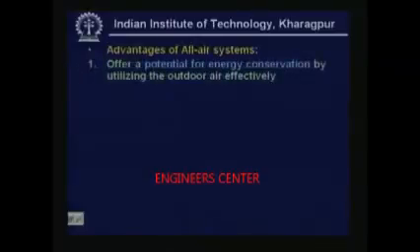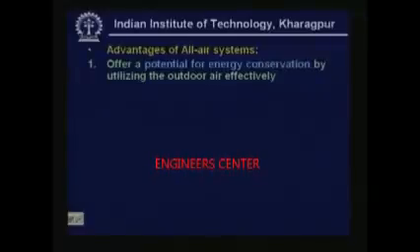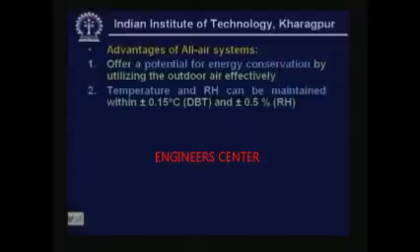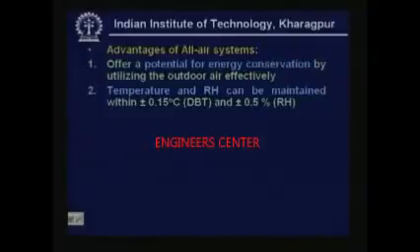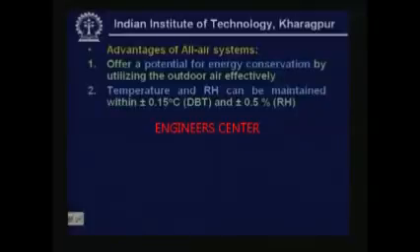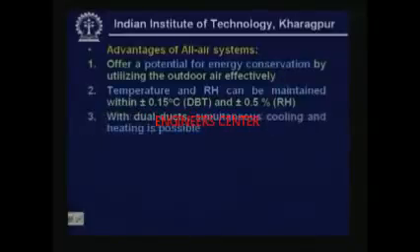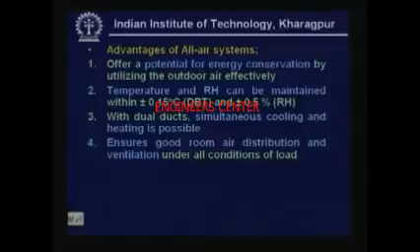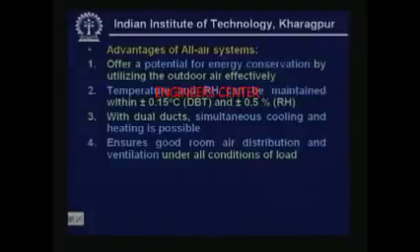Now let us look at advantages of all air systems. All air systems offer a potential for energy conservation by utilizing outdoor air effectively as just mentioned. Temperature and relative humidity can be maintained very precisely — temperature within plus or minus 0.15 degrees centigrade and relative humidity within plus or minus 0.5 percent — very close control. And with dual ducts, simultaneous cooling and heating is possible. All air systems also ensure good room air distribution and ventilation under all conditions of load.